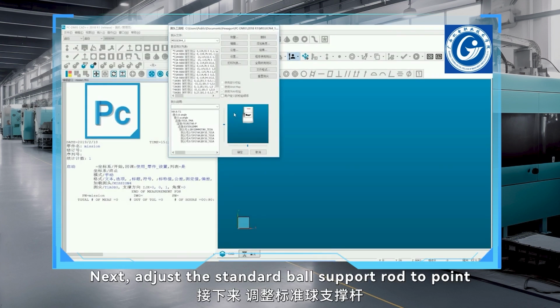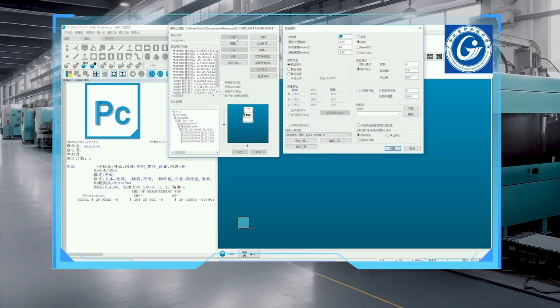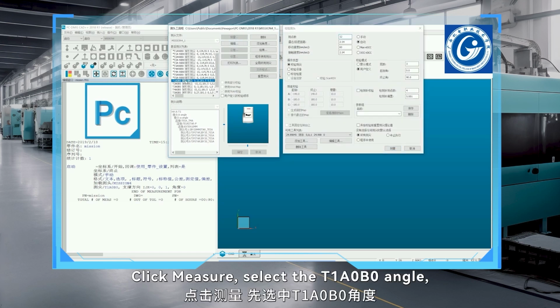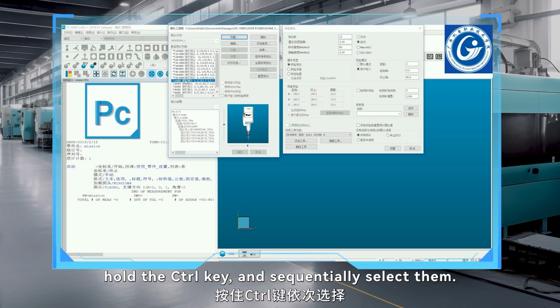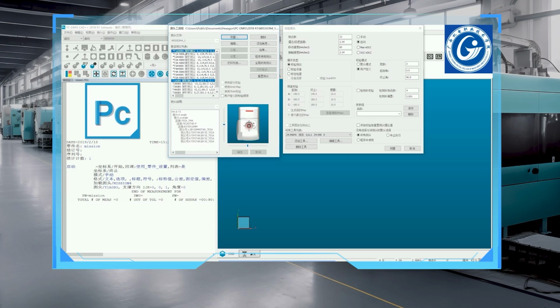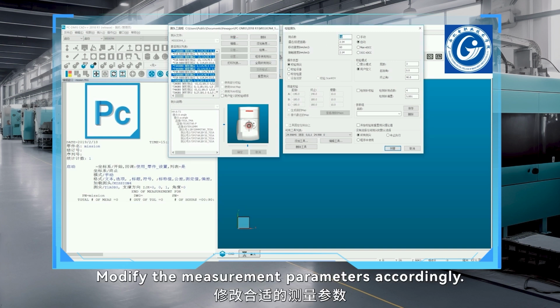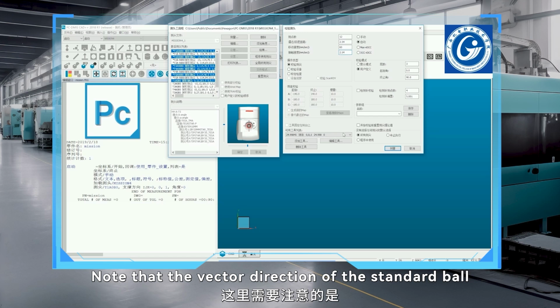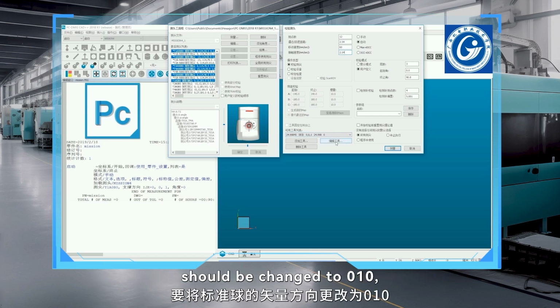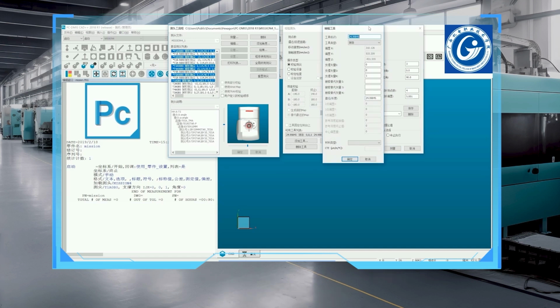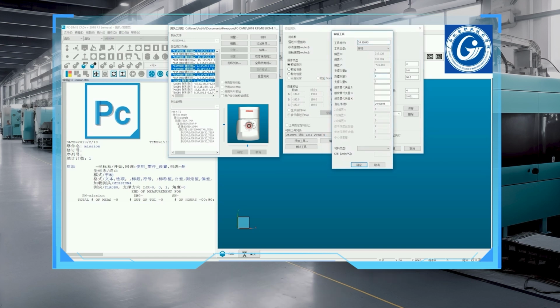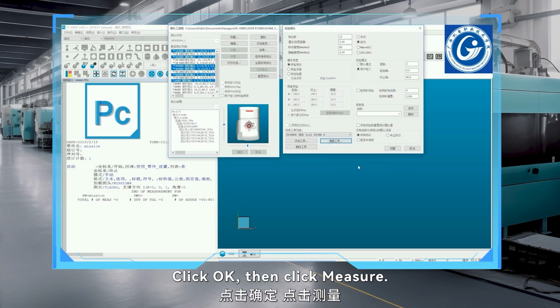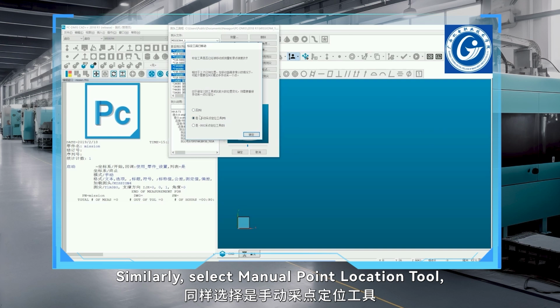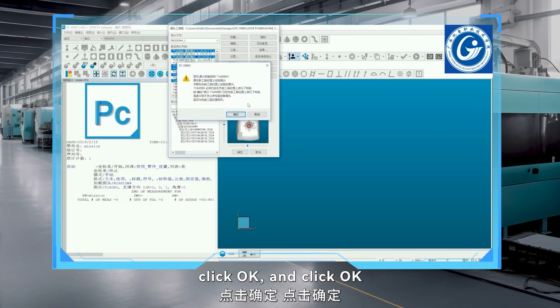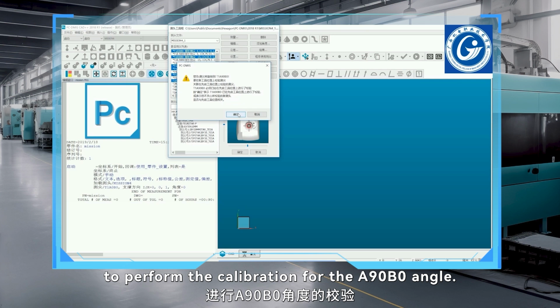Next, adjust the standard ball support rod to point in the positive Y direction. Click Measure, select the T1A0B0 angle, then select all A90B0 angles, hold the Ctrl key, and sequentially select them. Modify the measurement parameters accordingly. Note that the vector direction of the standard ball should be changed to 0, 1, 0, as it is pointing in the positive y direction. Click OK, then click Measure. Similarly, select Manual Point Location tool, click OK, and click OK to perform the calibration for the A90B0 angle.